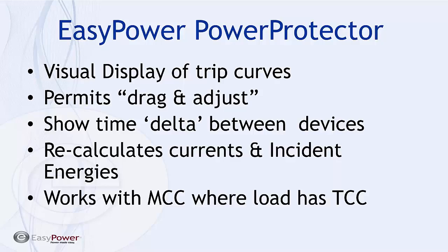The EasyPower PowerProtector module is the tool that permits the visual display of the performance curves. Some of the features that are built into it are the drag and adjust features that show what the performance and time differences would be as we make adjustments to the trip settings on a device. We can also show the time delta between devices, whether they're in the MCC control center or not.